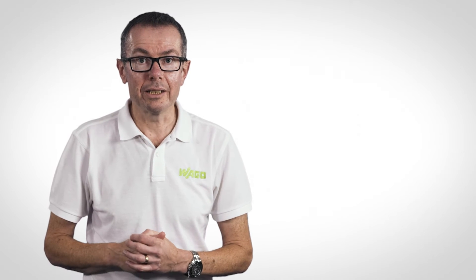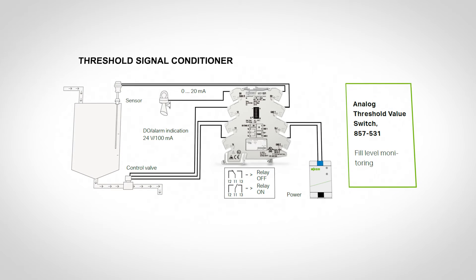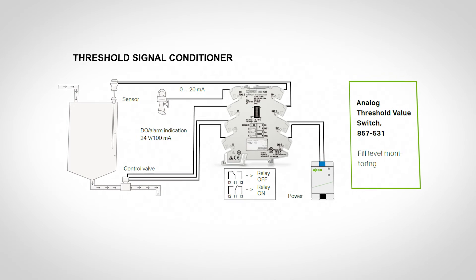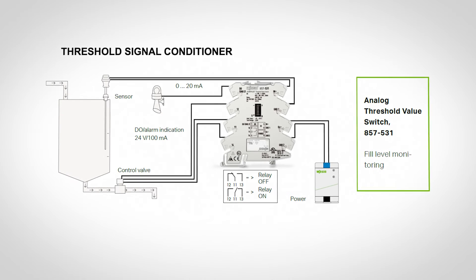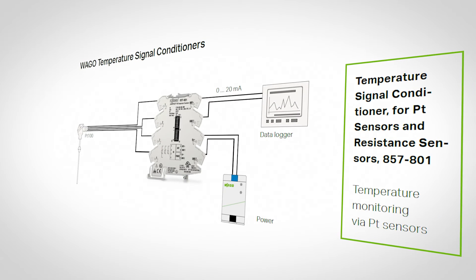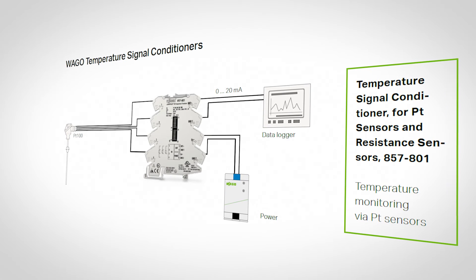Threshold value switches: these are essentially like a regular thermostat but are much more accurate, with either very low or adjustable hysteresis. The medium being measured can be any metric, as they accept voltage or current loop analog signals, or can accept directly temperature measurements using RTDs or thermistors.